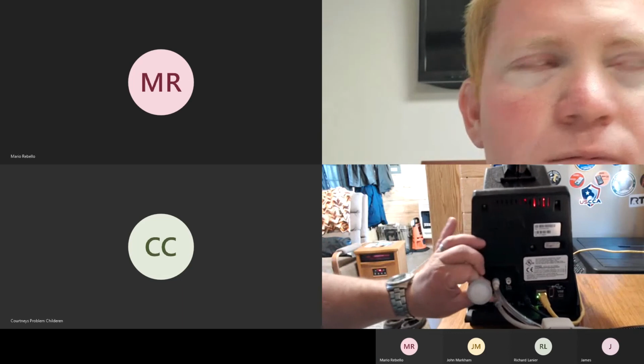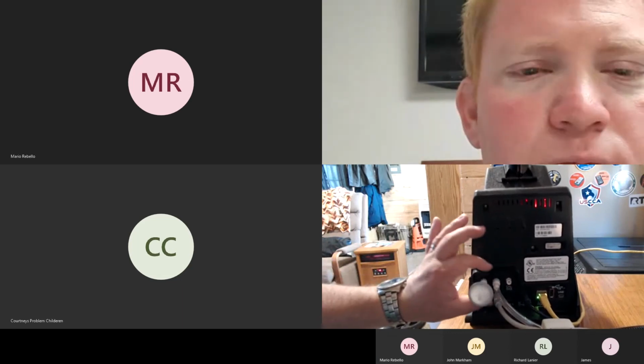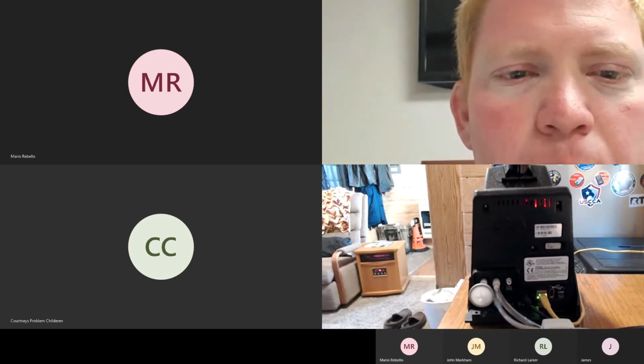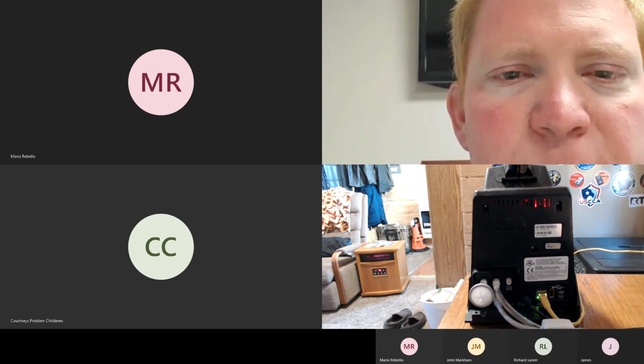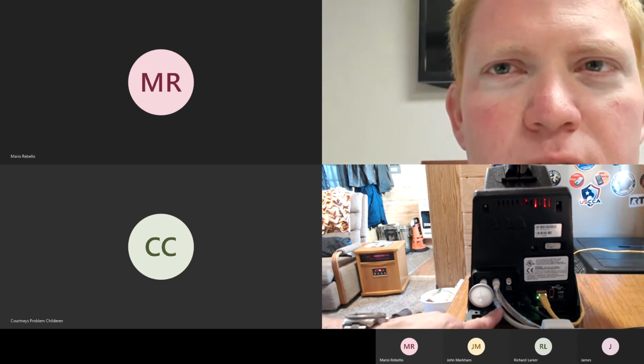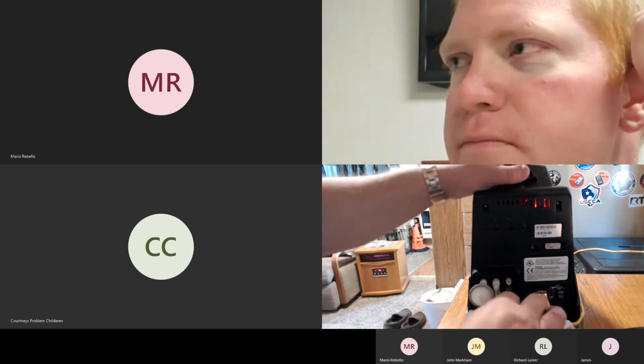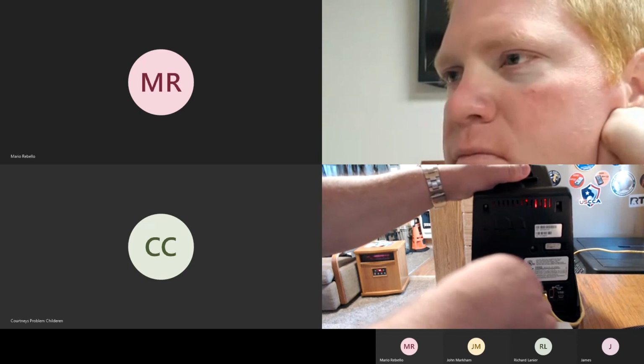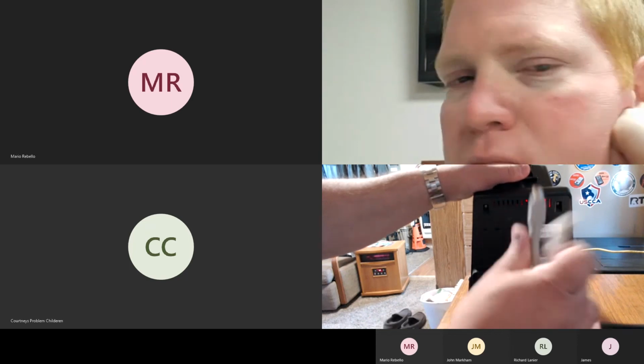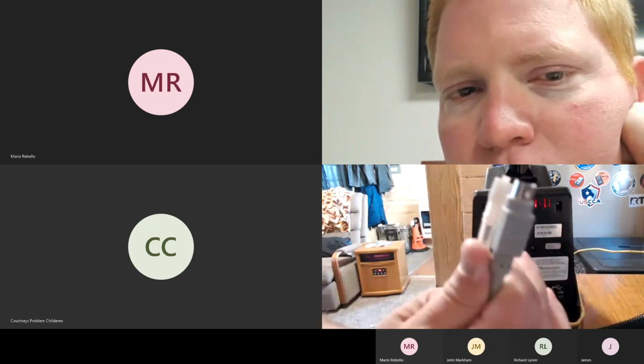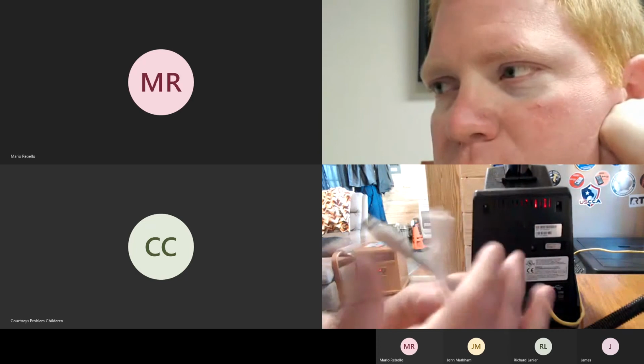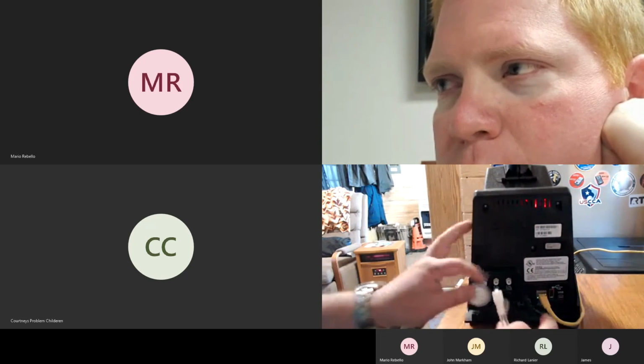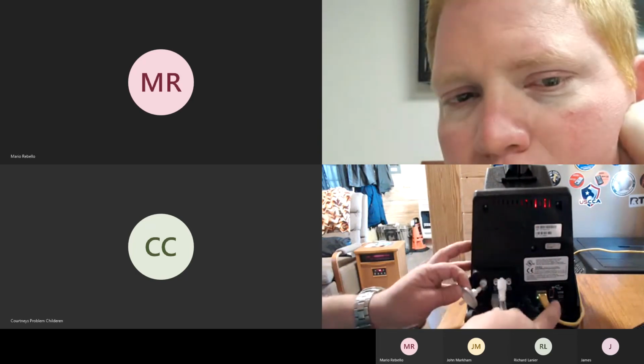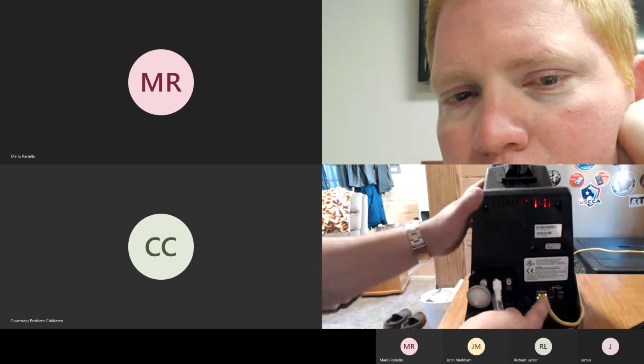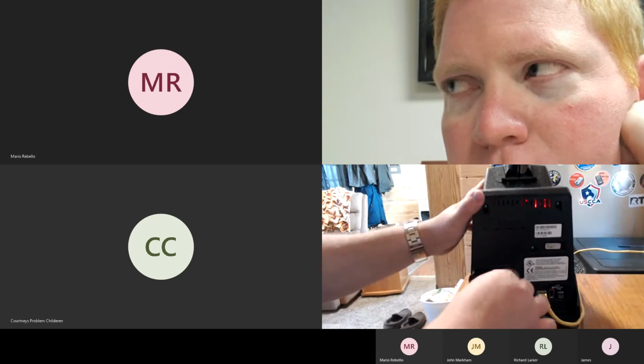The fresh air port should only have either this filter right here on it or a bottle of zero grade air, if you have an extremely dirty environment where you cannot utilize just the fresh air filter. Biggest thing to note back here is making sure that your tubing and your card reader assembly cables are all going to the same ports. So port number 2 right here is what I'm utilizing, and tubing goes on port number 2.